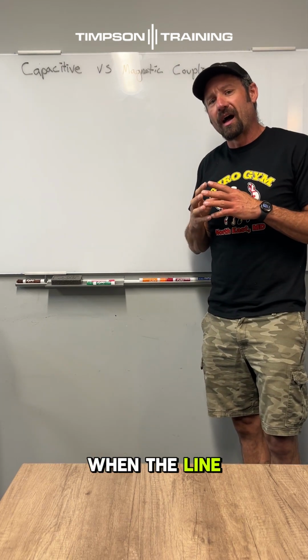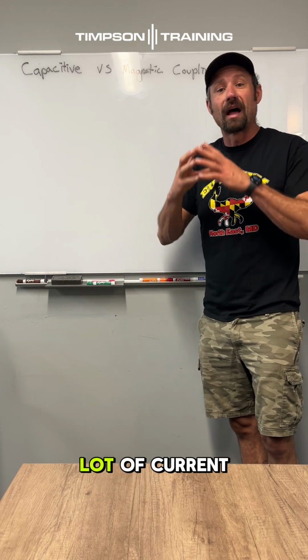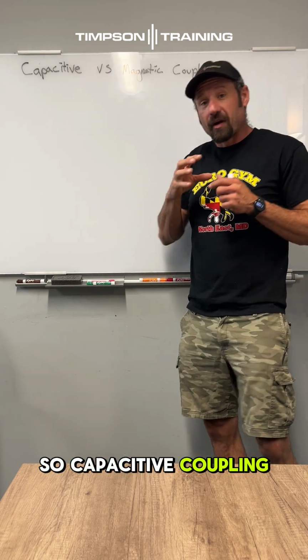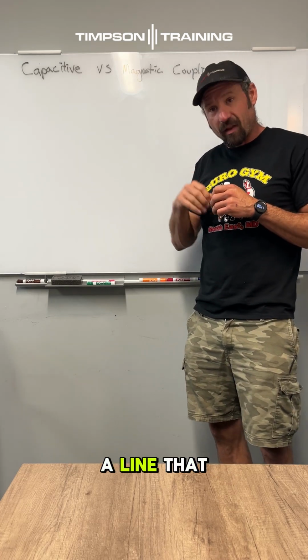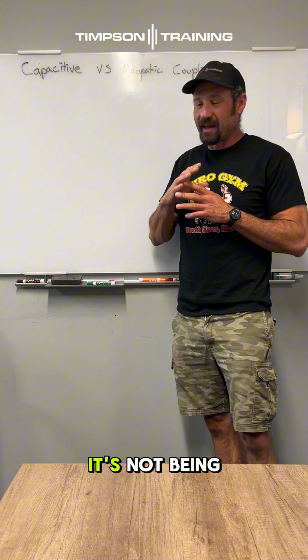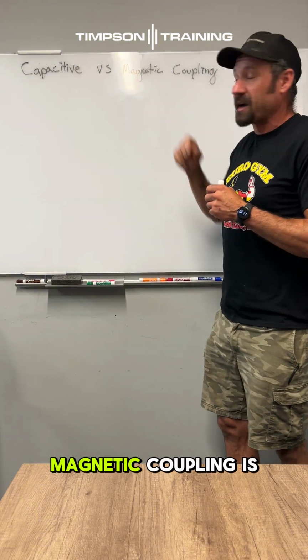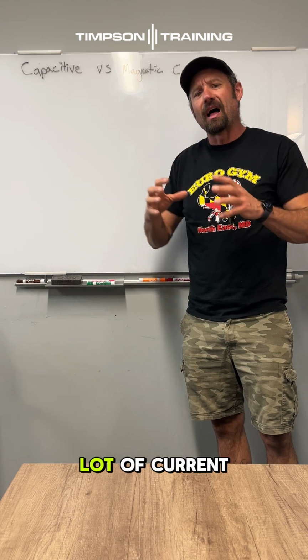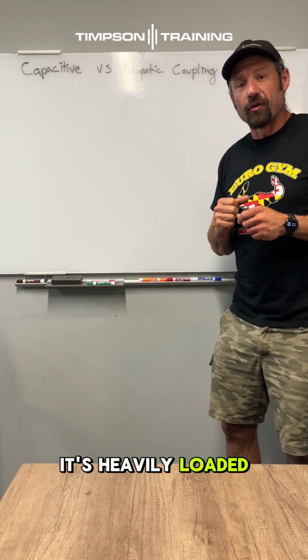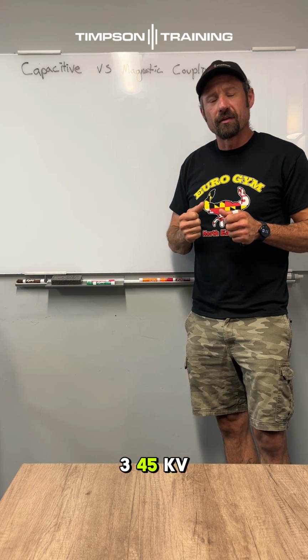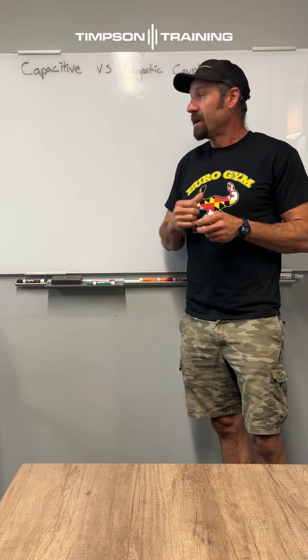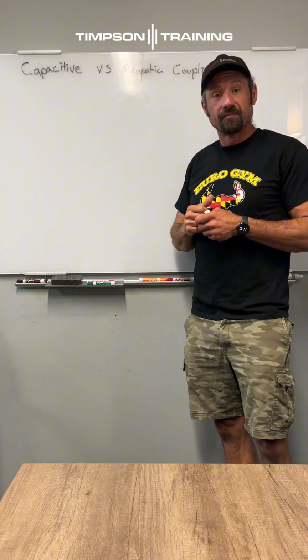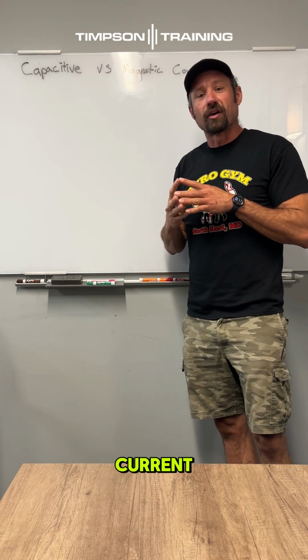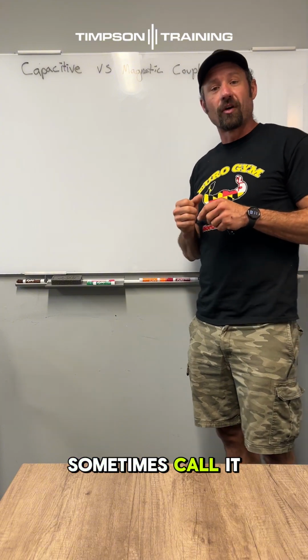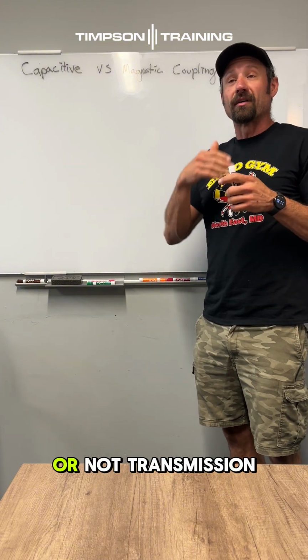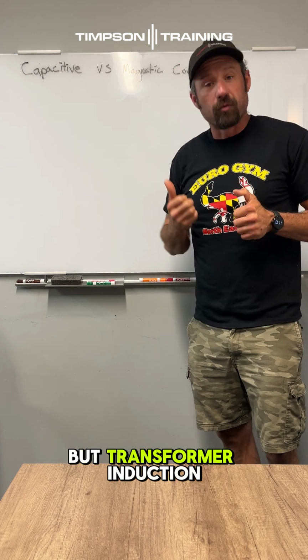Magnetic coupling is when the adjacent transmission line has a lot of current. Capacitive coupling only happens on an unloaded line, one that doesn't have much current on it, it's not being used heavily. Magnetic coupling is when we have a line that's heavily loaded, maybe we're working in a hot 345 kV transmission corridor. We've got a lot of current, and that current is inducing a current on the adjacent line. That's why we sometimes call it transformer induction.